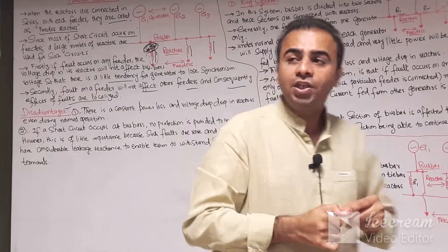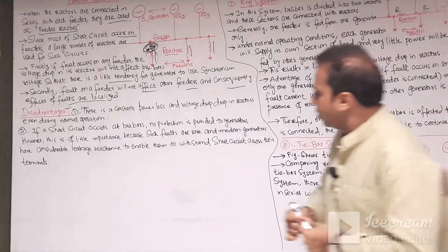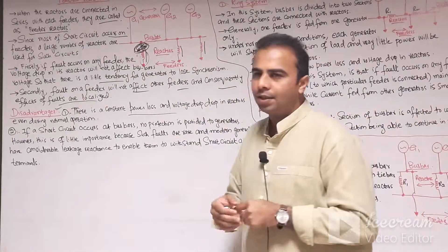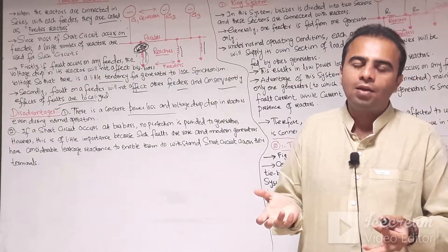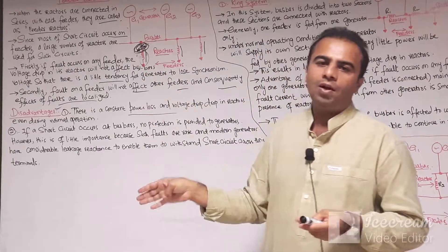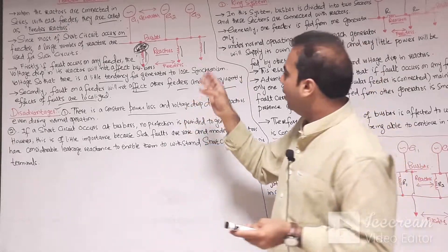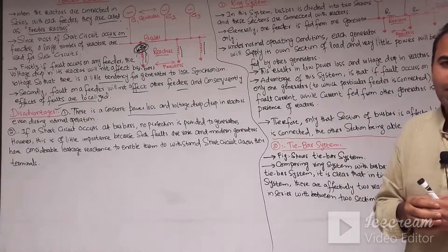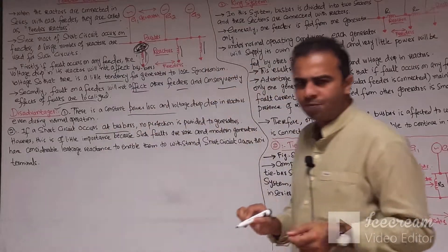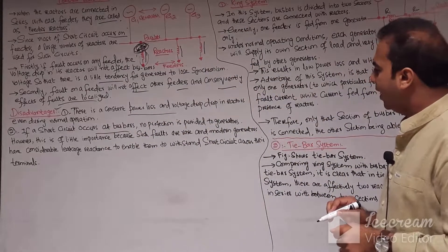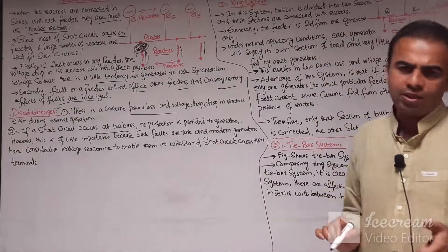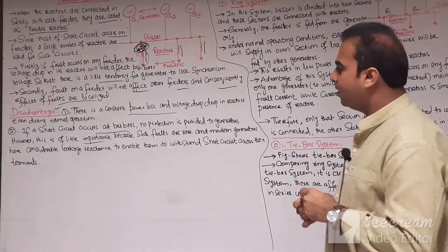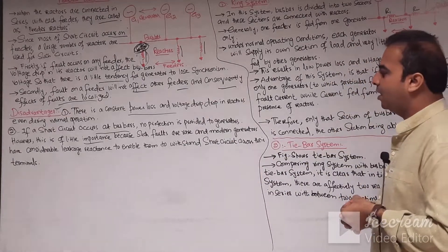Let us discuss the disadvantages of the feeder reactor. There is a constant power loss and voltage drop in the reactors during normal operating conditions, because reactors are leakage reactances — during normal operating conditions of any feeder, voltage drop and power loss across the feeders can be observed. Second, if a short circuit occurs at the bus bars, no protection is provided to the generator. However, this is of little importance because such faults are rare and modern generators have considerable leakage reactance to withstand the short circuit current.